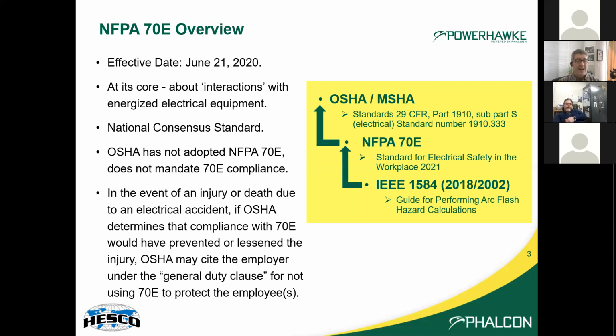NFPA 70E is not code. It will likely never be code necessarily, but it's known as a national consensus standard. It has not been adopted by OSHA, and OSHA doesn't mandate specific compliance with 70E. However, if you should be so unfortunate to have to deal with an injury or death due to an electrical accident, and if OSHA determines that compliance with 70E could have prevented or lessened this, that's where the citation would come in.